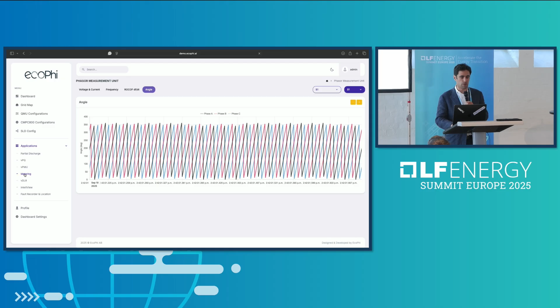So thanks to the accuracy of the measurement that we have, we can also turn all of the metering devices into a virtual application as well, measuring the active power, reactive power, and apparent power, anything that is needed. When it comes to capacity, if you know the partial discharge, power quality, high frequency issues, low frequency issues, and GIS information, you no longer need to install, for example, a thermometer to be able to do capacity analysis. You can do everything in real time, online, and know what capacity this transformer has. Both transformer rating and line rating you can do.